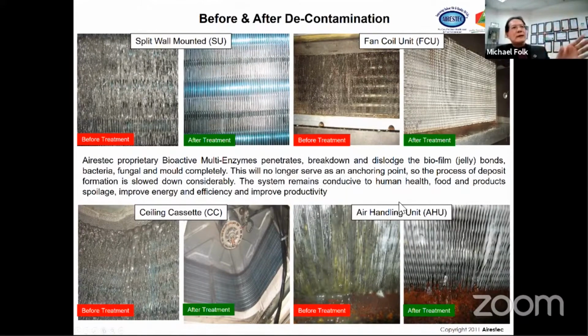Bottom right-hand side, you see the air handling unit, the giant units you find in big buildings. You see a lot of mold and fungus and biofilm oozing out towards the bottom. This is a sign that it's actually overflowing in the midsection of this AHU, which are very big in nature - they can be 6 feet or 8 feet or 9 feet tall. It means the whole thing is filled with biofilms. It's all coming out, and there's a lot more at the bottom.